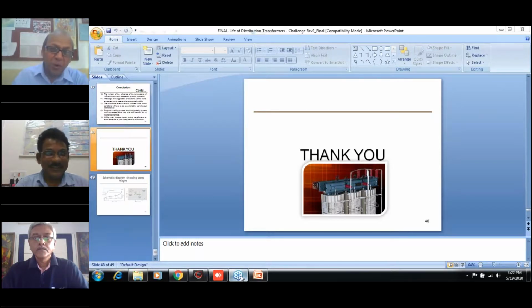But it is a time bound problem. I again ask, why did you change your house wiring? See, house wiring also, when it is done, it passes all quality tests, whatever quality tests it will pass. But reliability is different - reliability is with time. Creep takes time. When creep is in place, then it happens. You were seeing your plugs burning in the house earlier - when you take a 5 ampere plug and flow 5 ampere current, it will burn. Why was it burning? The reason was only the joint of aluminum. I was not knowing at that time, I was saying aluminum is big or light. But why is it happening? When we study, yes, it is because of the creep. That is the reason - it is a quality and reliability issue.